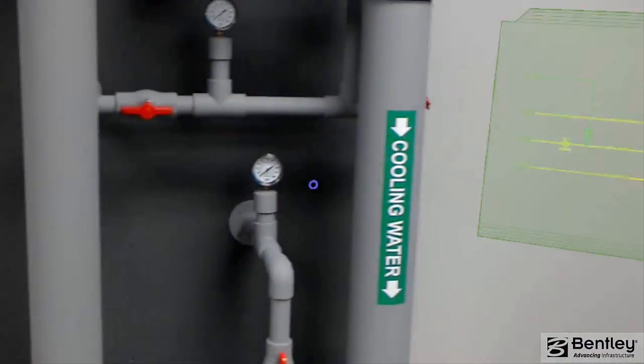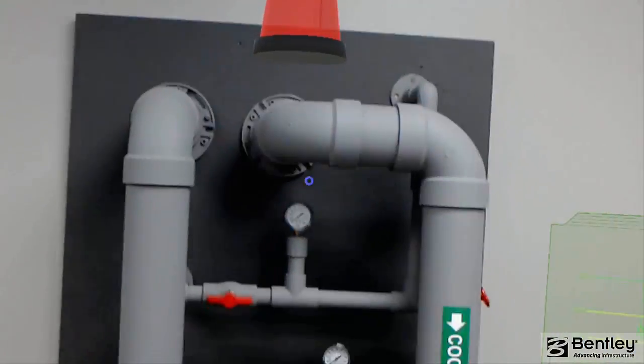Describe Alarm. Pressure at instrument PIT 5003 is below 2 PSI threshold. Current pressure is 1.5 PSI. Okay, PIT 5003, that's the one.